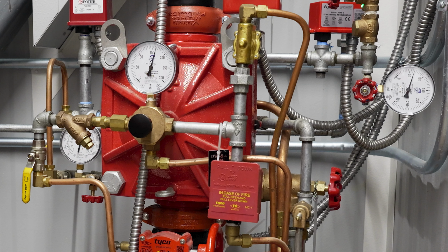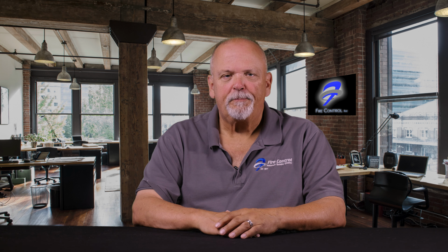All of the pre-action systems in the building are designed to operate with air pressure of 60 psi. The QRS switch is configured to expect this pressure and will send the supervisory signal if the air pressure goes 5 pounds above or below that point.